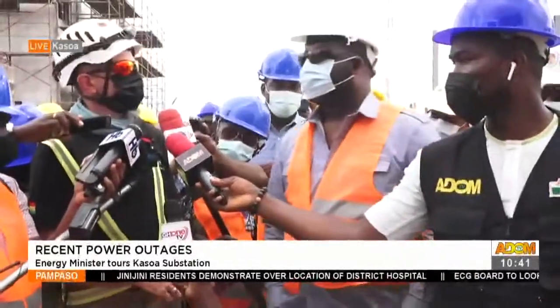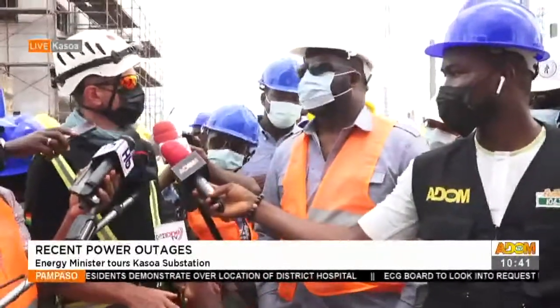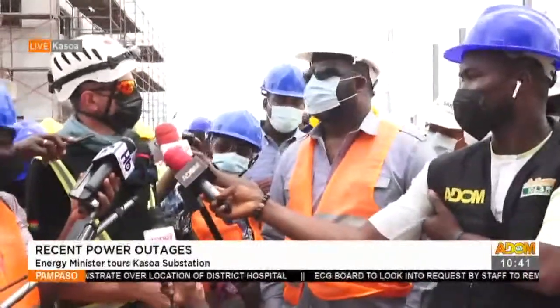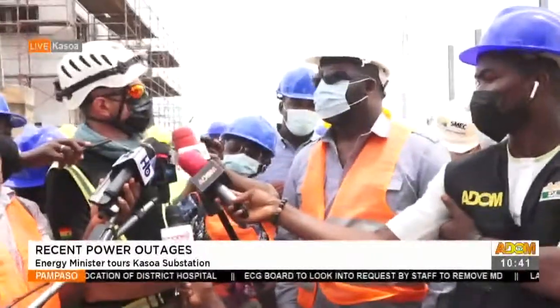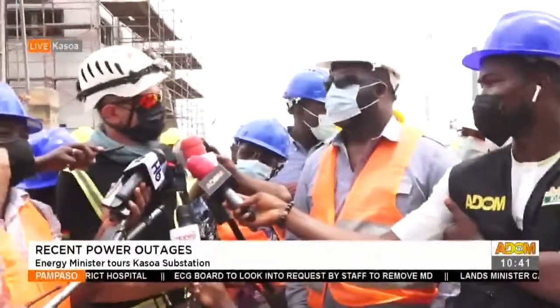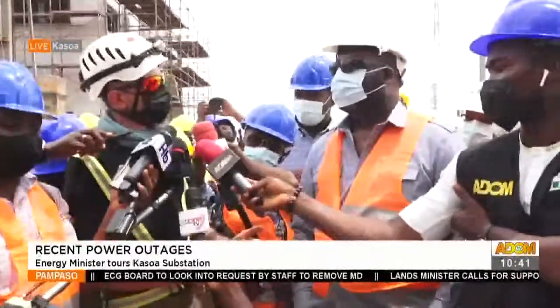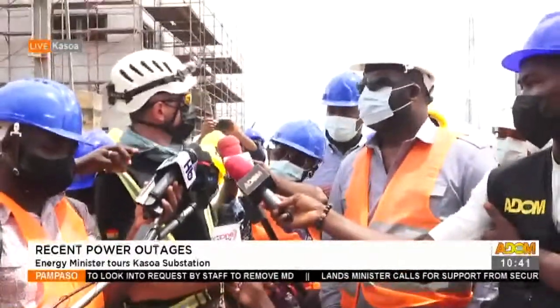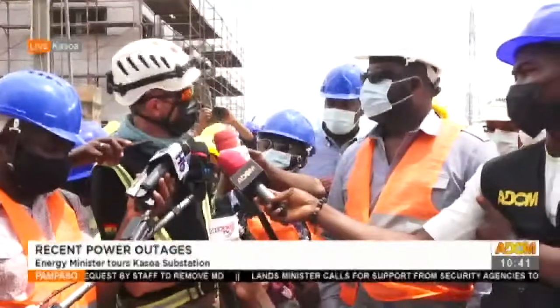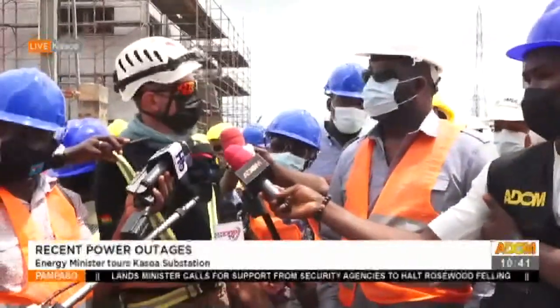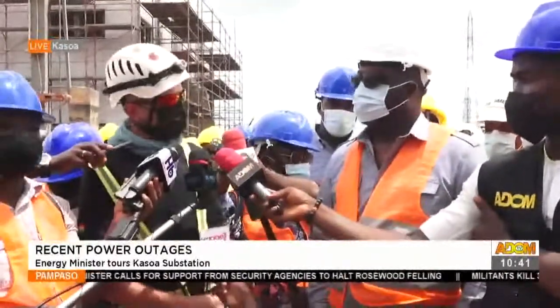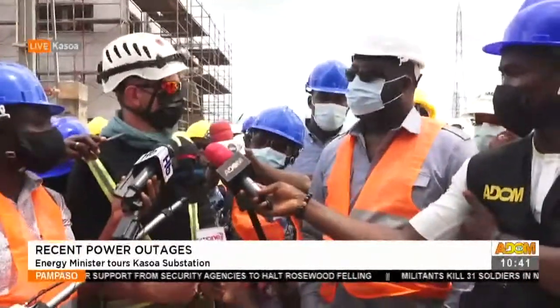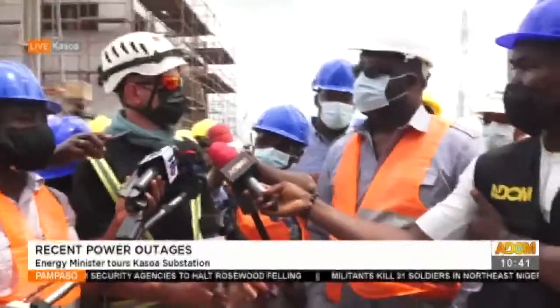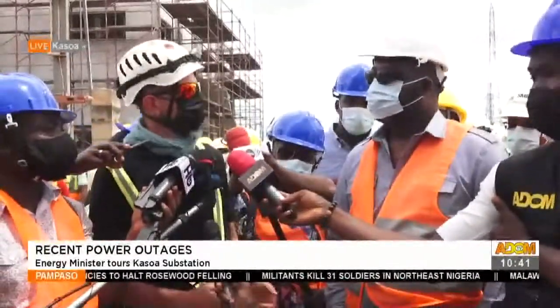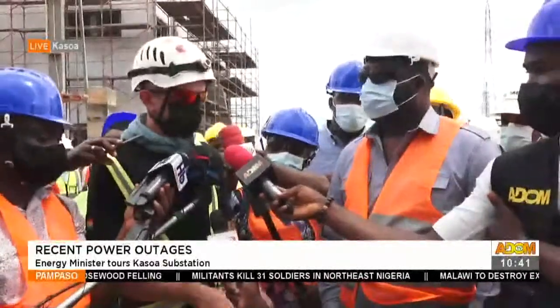But when we connect the substation, it doesn't mean we can energize all the feeders and everything in one day, of course. It means we will first energize the 161 kV GIS, and then step by step we will energize power transformers. If everything is okay, we will energize this outdoor MV equipment on gridco side. If everything is okay, then we'll energize ECG side. If everything is okay, we can start connecting ECG feeders. So after the first energization of the substation, of course, we need weeks of commissioning and until final completion.